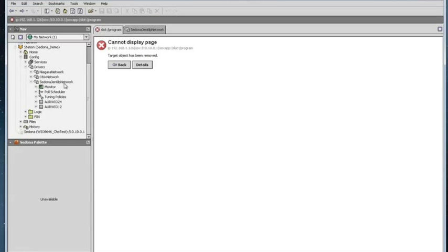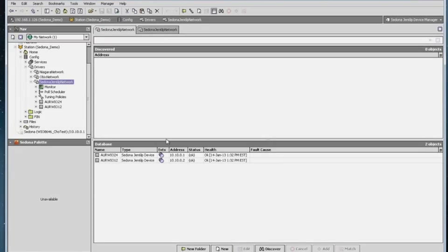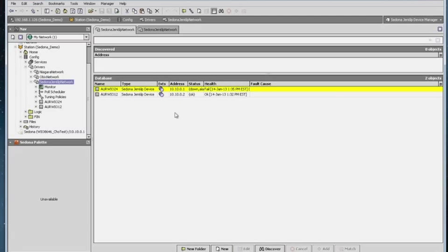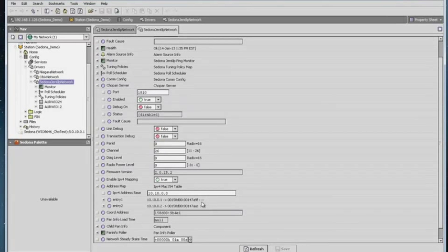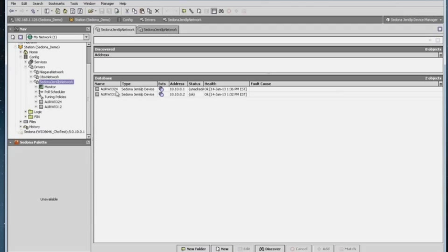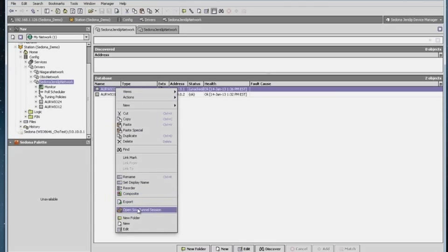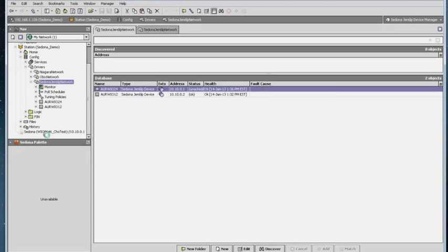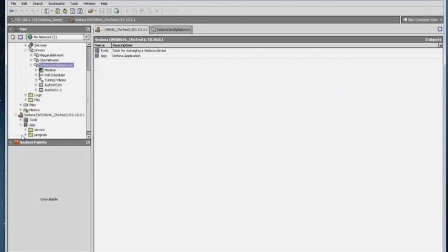The device fell offline. If we go back to our Sedona network immediately, you see it drop off. It should come back relatively quickly. And this again is where you can go back and forth from your network here and watch the RF. So we saw it go yellow in the Sedona network. It's back okay there. So if we come back here, he's back healthy. So we can enter into this SOX tunnel session again and go into the program.